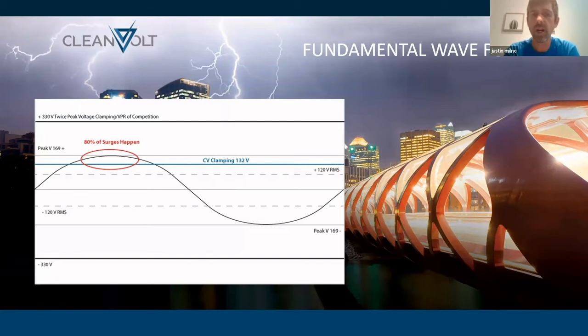The reason we like to share this is where you see the blue line at the CV clamping. This is where manufacturers, if you open up their owner's manuals, will typically have disclosures stating that the device has a 10% tolerance of RMS level, and that this is the safe zone. So if it's a computer running off of 120 volts, they're saying that 132 volts is the safe zone of that connected computer.